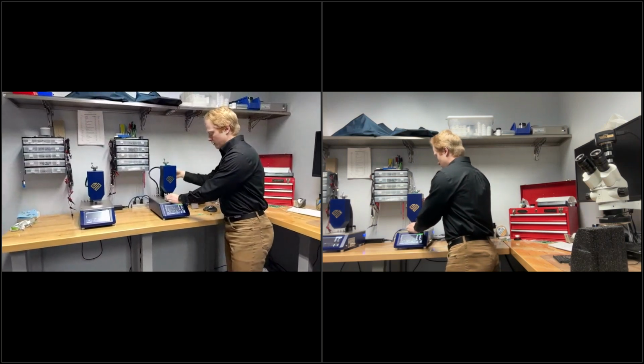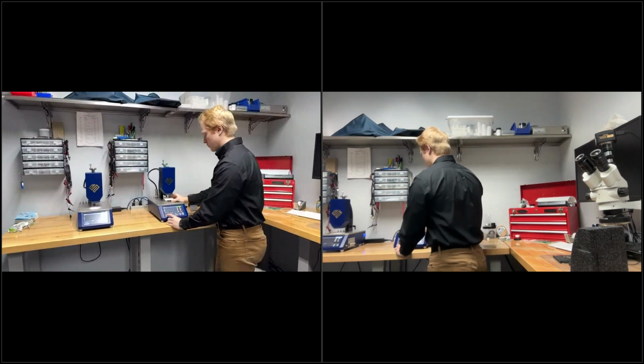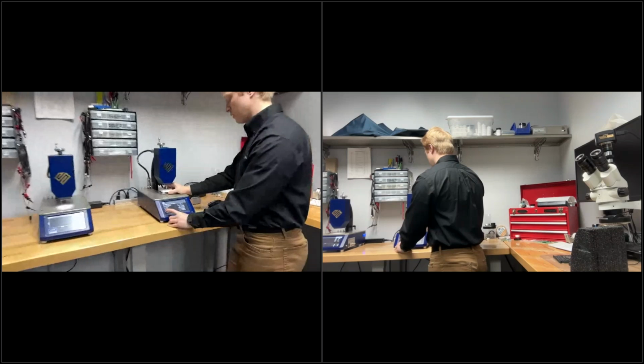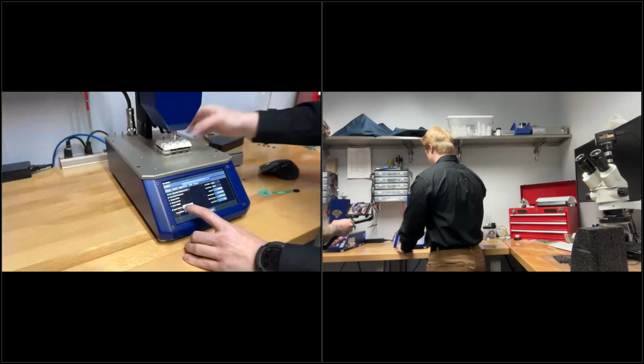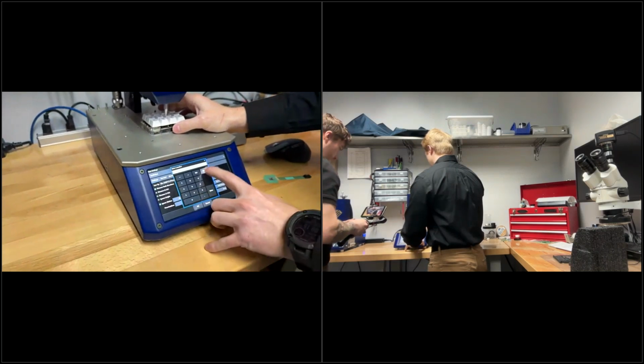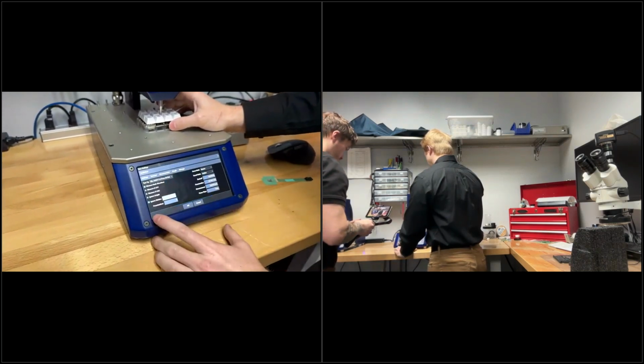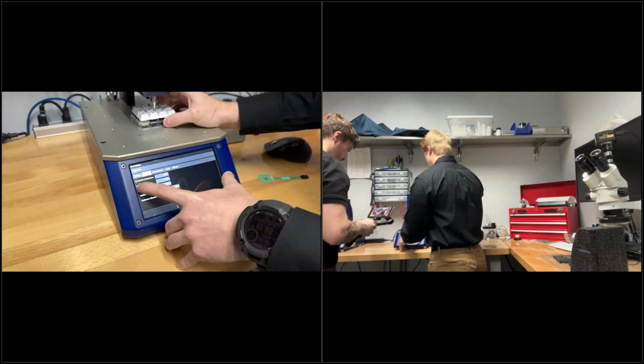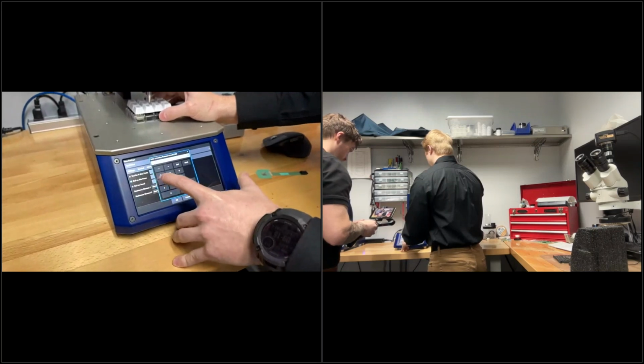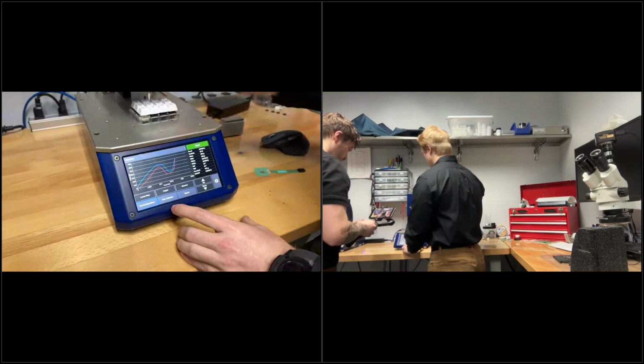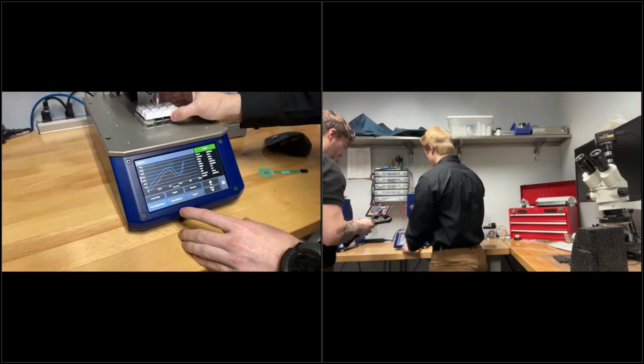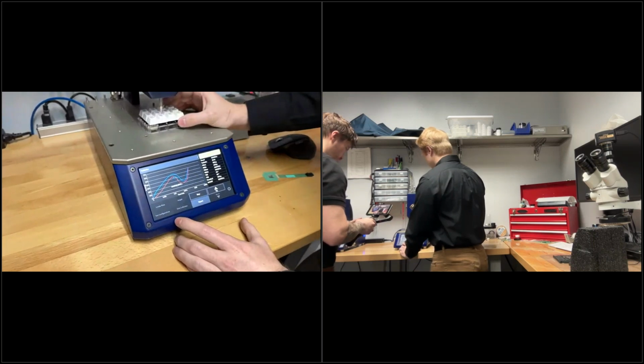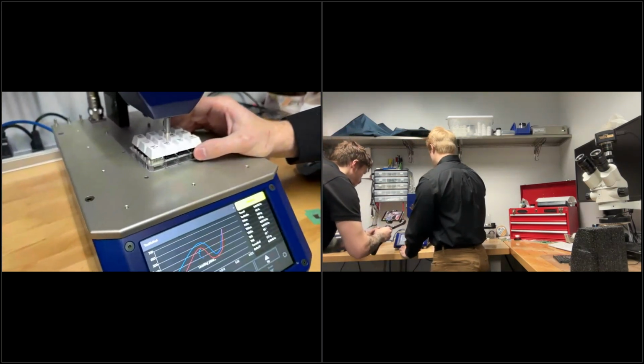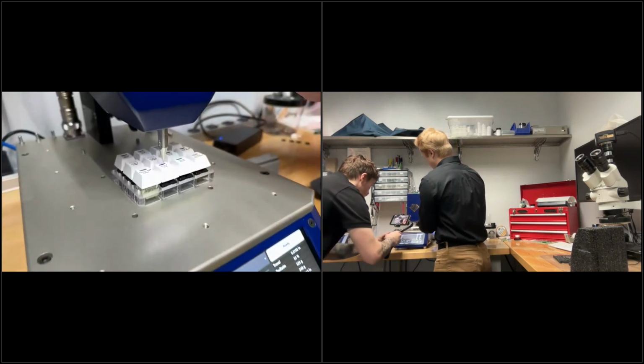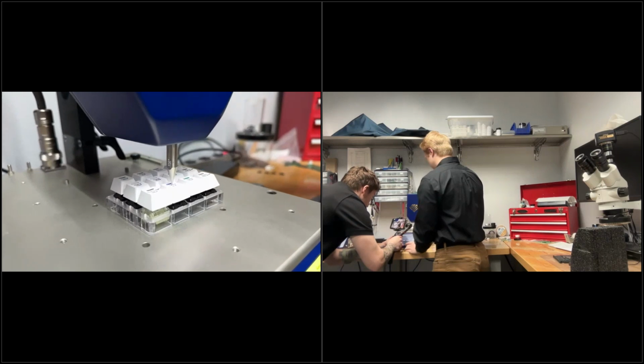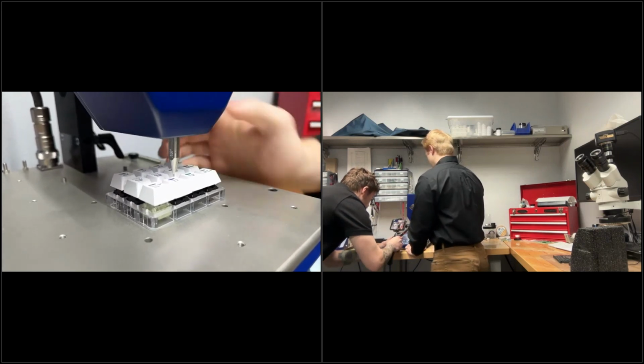Now these are very different characteristically than your typical dome switch. So I'm going to change up some of the settings here to be more in line with this style switch. I'm going to adjust the stiction setting here to be more in line with that, and a test. We're going to end on an absolute final force of 100 grams, since most of these are anywhere from the 40 to 60 gram force range. So we'll come down, we'll locate the plate. I might have to adjust the head down just slightly to give it enough travel. Right, and then we will measure from there.